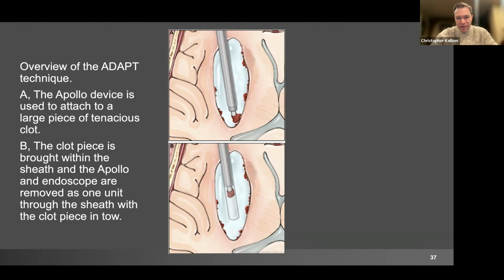But you can see here that you can't pull that wand into the endoscope or it will pop off the end of it essentially, and you'll bring in the wand and then lose suction force. You'll lose your connection to the blood clot. So you need to pull out the endoscope and the wand together without pulling the wand into the endoscope.